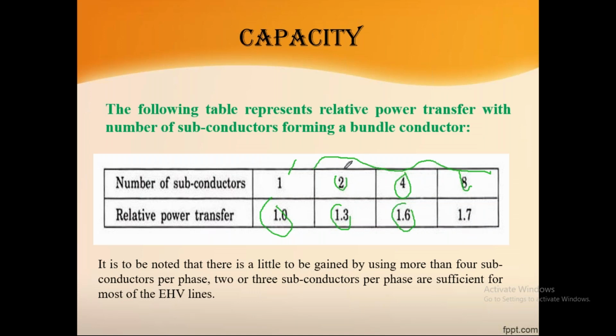Generally in India we are using bundle conductors only with 2, 3 and 4. So we are not using 8. What is the reason? If you observe 2, 4 and 8, in between there is only a 0.1 difference. If you are using 8, the conductor requirement is more and the cost will be more. So that's why they mostly prefer 2, 3, 4 based on the voltage levels. They won't go for 8 because its capability is less, with just a small difference between 4 and 8.